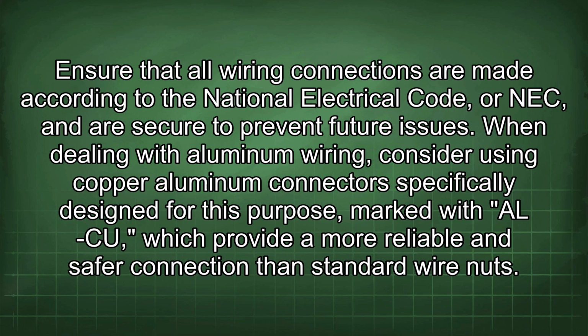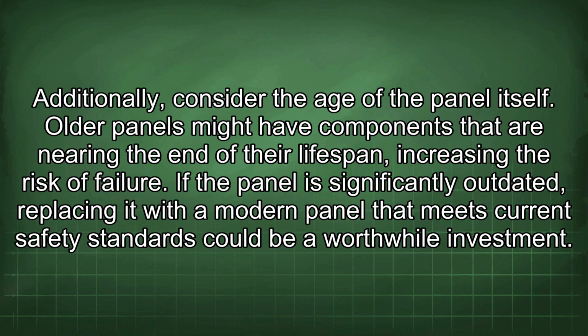Ensure that all wiring connections are made according to the National Electrical Code, or NEC, and are secure to prevent future issues. When dealing with aluminum wiring, consider using copper aluminum connectors specifically designed for this purpose, marked with ALCU, which provide a more reliable and safer connection than standard wire nuts. Additionally, consider the age of the panel itself. Older panels might have components that are nearing the end of their lifespan, increasing the risk of failure.